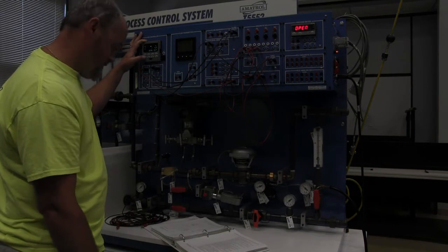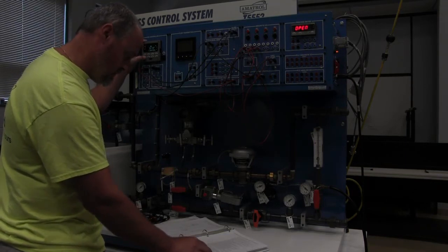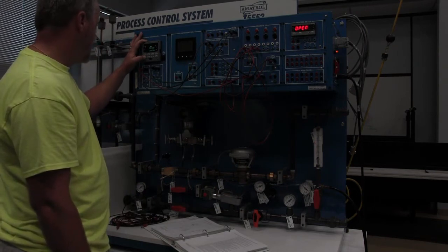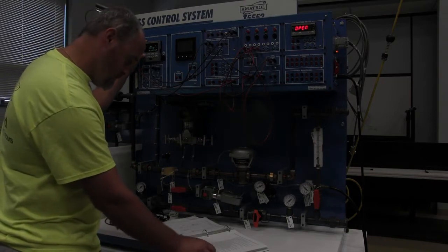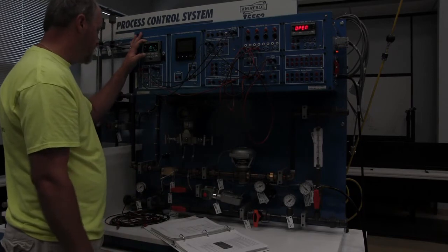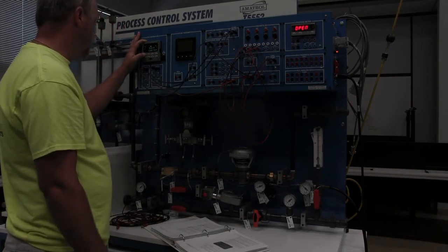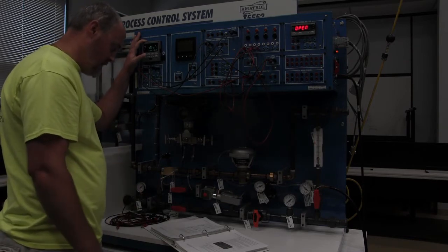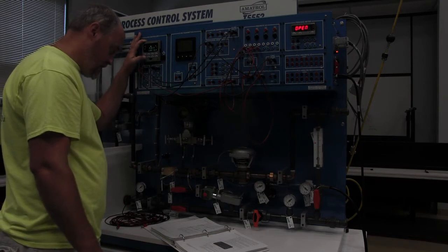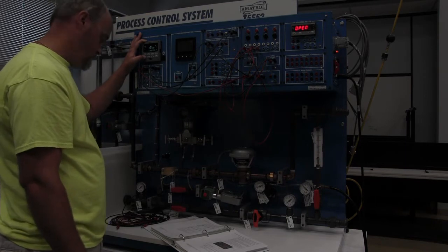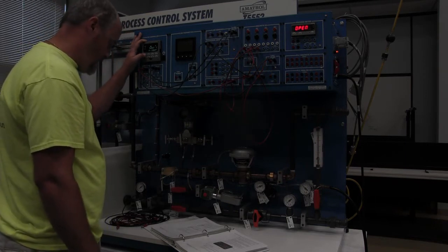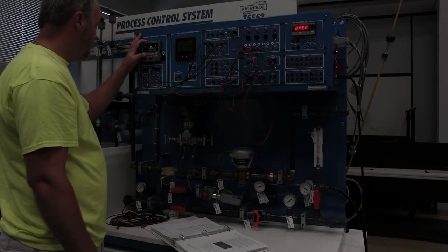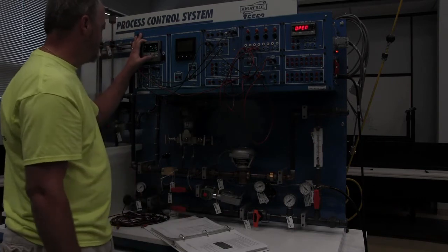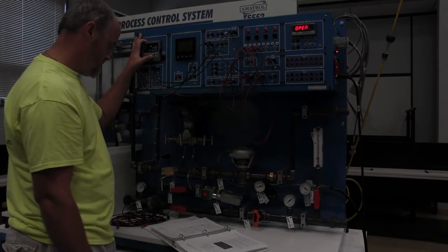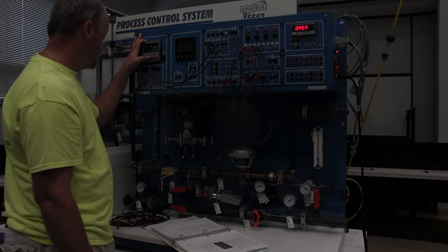So now we're going to lower display to setup menu, and we're going to go find algorithm. Once we find that, we're going to press the function loop key till we see control. Oops, was already there. Control algorithm. We're going to make that PIDA, which we're already there. And then to scroll, we're going to find control now. Once we find control, we're going to press the function loop key. Set point high, we want that to be 10. I think I just set that to 27, so.